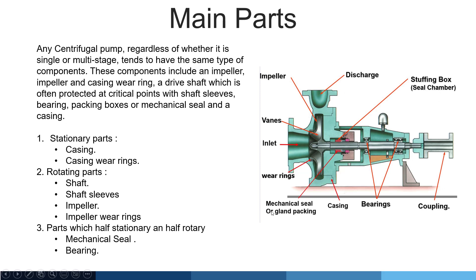Now we will see the main parts of the centrifugal pump. You can see in the pictures. Some of the main parts are impeller, casing, bearing, coupling, mechanical seals and gland packing, inlet, bearing, discharge and suction head. Any centrifugal pump, regardless of whether it is single or multi-stage, tends to have the same type of components. These components include an impeller, casing, bearings, a drive shaft which is often protected with shaft sleeves, packing box or mechanical seal, and a casing. The parts can be divided into three types: stationary parts, rotating parts, and parts which are half stationary and half rotating.